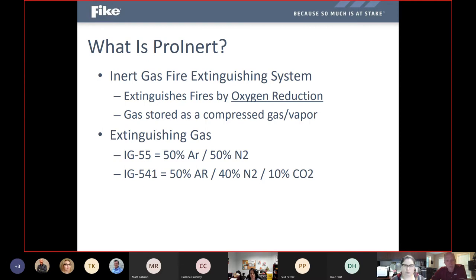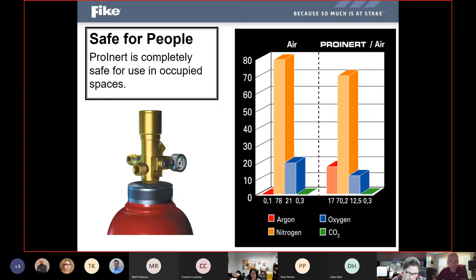But with a Pro Inert system, it looks to use a combination of primarily argon and nitrogen to reduce the oxygen in the area to below levels where a fire can continue to burn, but to keep it above limits and minimal balances of oxygen to where it's still safe for human occupants inside the room. So if we look at what that really means, on the left-hand side there is the typical air that we breathe right now: a trace amount of argon, 78% nitrogen, 21% oxygen, and a trace amount of CO2.